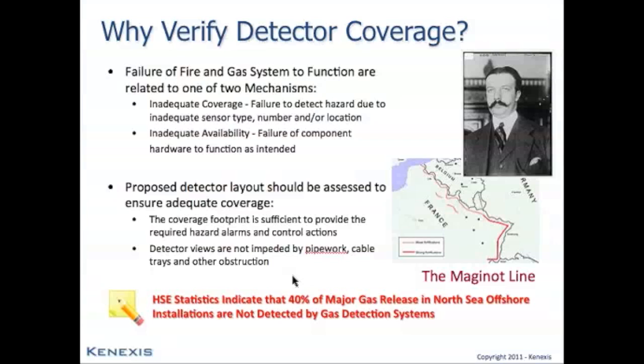With respect to detector coverage and probability of failure on demand, an important statistic was generated by the UK Health and Safety Executive, HSE. What they determined was that 40% of major gas releases in the North Sea, these are not pinhole leaks or small transients, but major gas releases, 40% of these major gas releases were not detected by the fixed gas detection systems that were in place. Again, this strongly indicates that you have a coverage problem with existing gas and fire detection systems as opposed to an integrity problem.